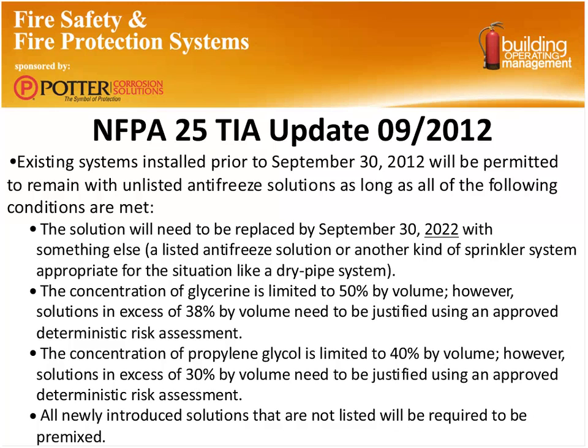The concentrations of glycerin are limited to 50% by volume, and anything over 38%, which was in that previous recommendation, needs to be justified by an approved deterministic risk assessment. That's kind of hard to determine. Who's making that determination? The industry really hasn't defined that very well yet, but we'll see more on that as this progresses. The concentration of propylene glycol is 40%, and again, anything in excess of 30% needs a justification. And premixes are required when the products are newly introduced.